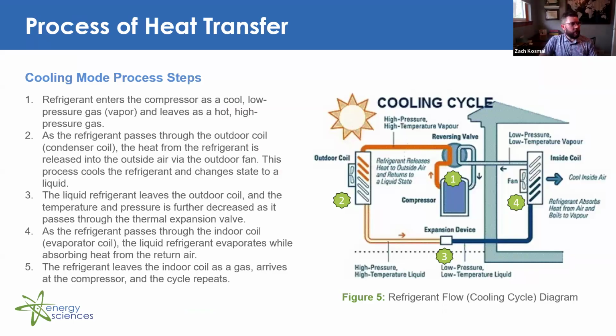So I just want to touch on the process of heat transfer a little bit. The figure on the right is the refrigerant flow in a heat pump. This is the cooling cycle specifically, so it's a reverse flow of that refrigerant from the first figure on the first slide. If you start at 1 at the compressor, the refrigerant enters the compressor as a cool, low pressure gas or vapor, and it leaves as a hot, high pressure gas.